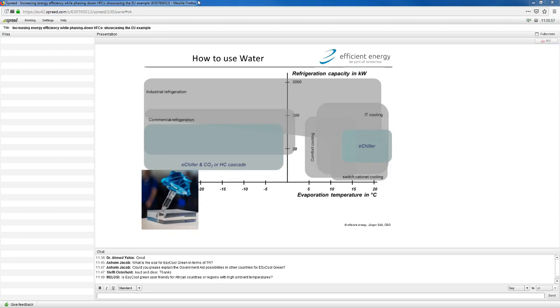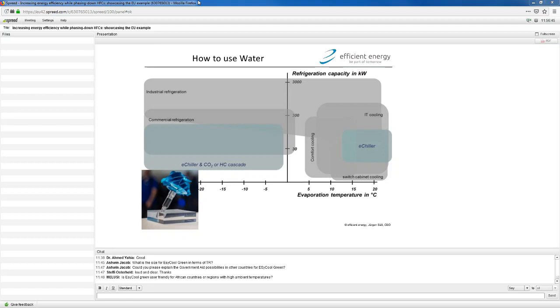What you can see on the right-hand side, the e-chiller application range is mainly addressing IT cooling, so that means server cooling. It's comfort cooling, it's not so much air conditioning due to humidification. It is cabinet switch cabinet cooling, and it is industrial refrigeration, so that means like plastic molding and stuff like that. We try to stay above temperatures about like, well, let's say we start from 12-15 degrees like that, and then not to go too far down because of the vapor curve of water. A very interesting application on the left side of the chart is to actually use water as a refrigerant together with other refrigerants like CO2 or hydrocarbons, and this in a cascade.